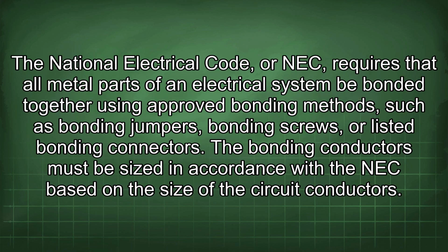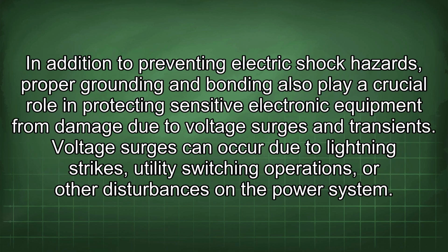The National Electrical Code, or NEC, requires that all metal parts of an electrical system be bonded together using approved bonding methods such as bonding jumpers, bonding screws, or listed bonding connectors. The bonding conductors must be sized in accordance with the NEC based on the size of the circuit conductors. In addition to preventing electric shock hazards, proper grounding and bonding also play a crucial role in protecting sensitive electronic equipment from damage due to voltage surges and transients.